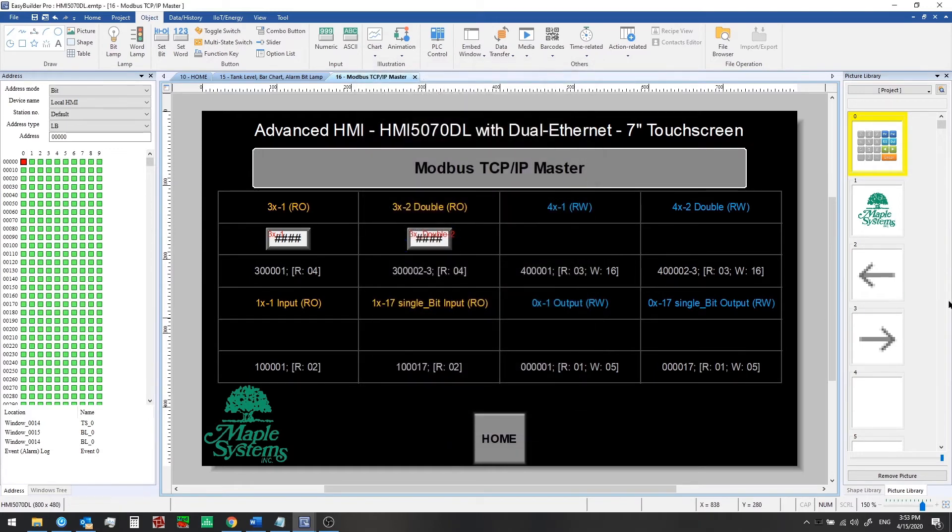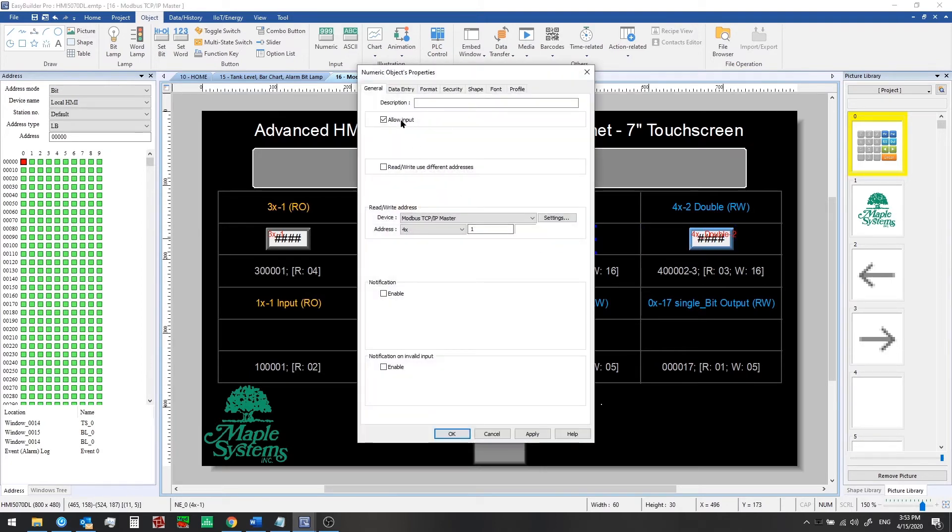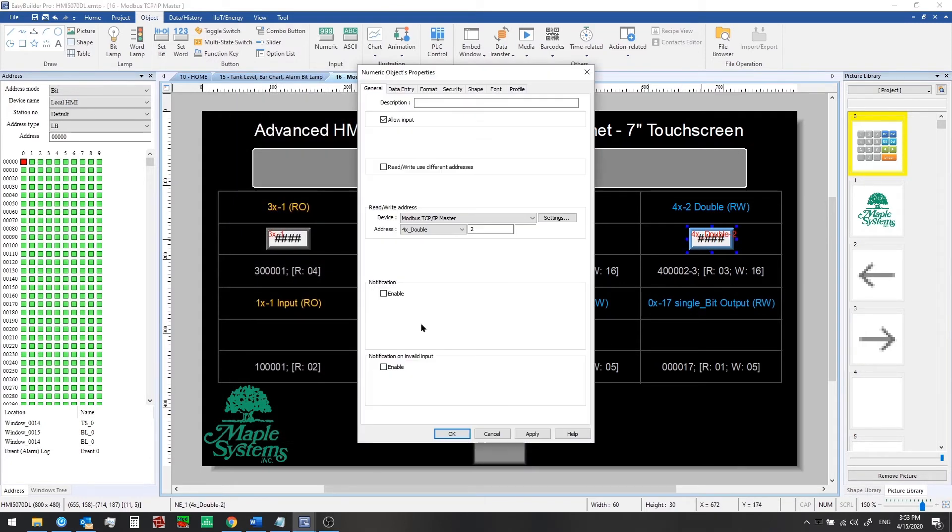Next, we're going to copy over some holding or output registers. These will be numeric input objects. For these, we're allowing input, and we're choosing from the 4x device type here. So it will be 400,001 is the first address. A 4x double would read two registers starting at this reading address, so it would go from 400,002 to 400,003.